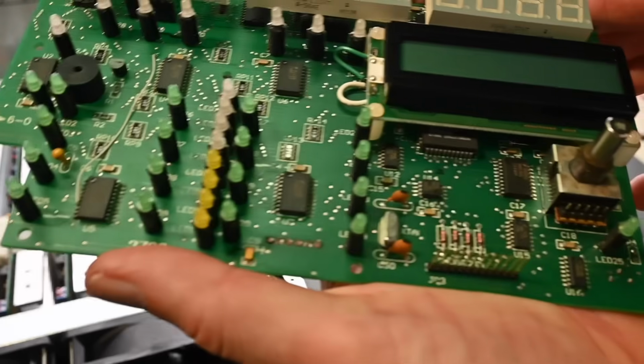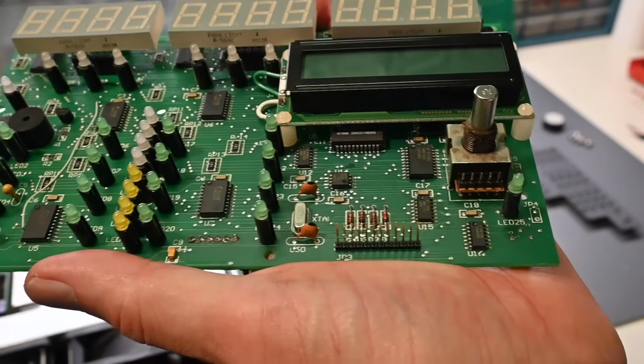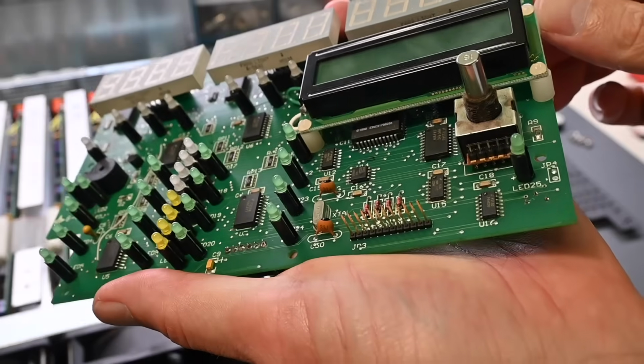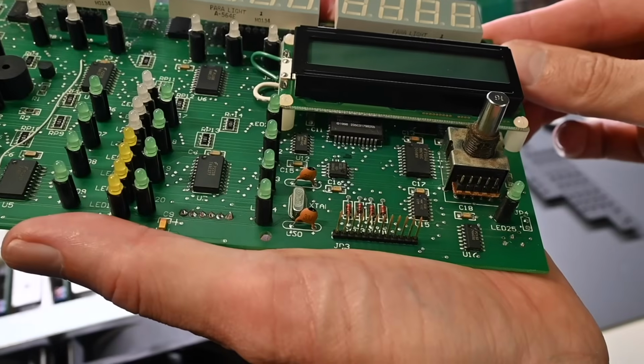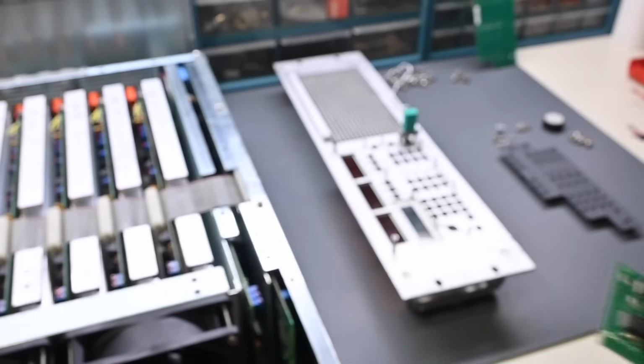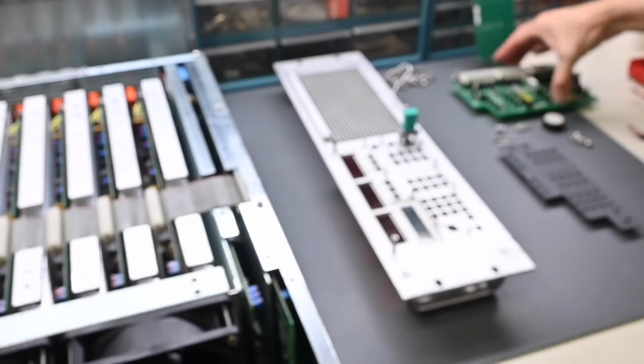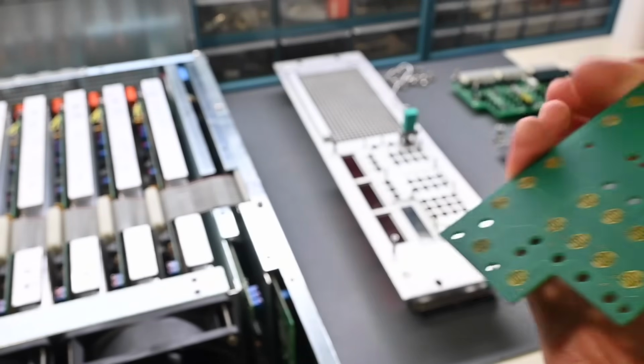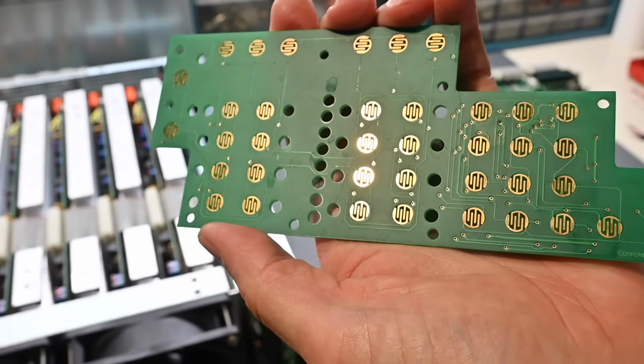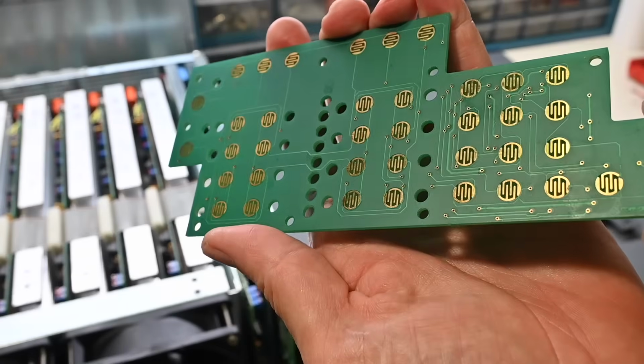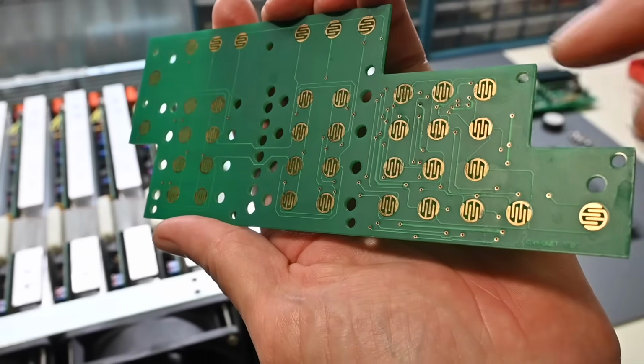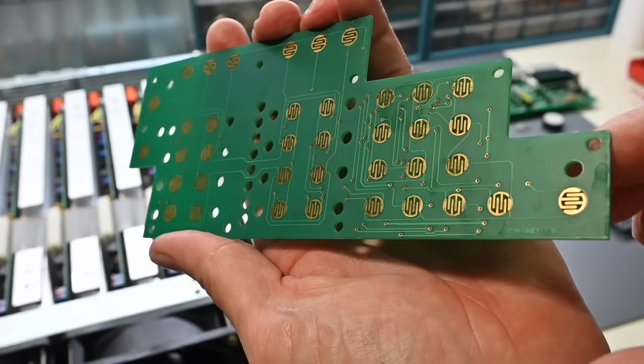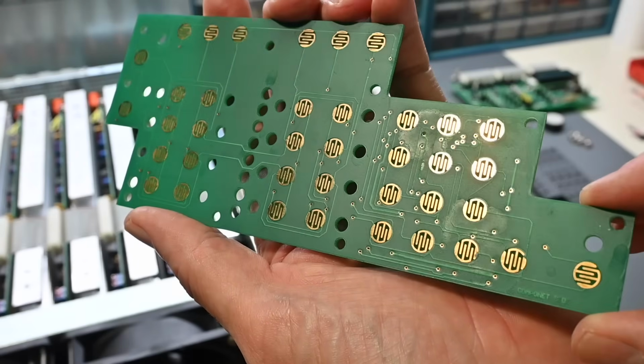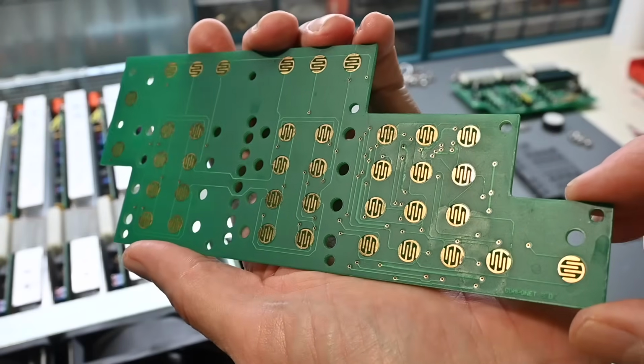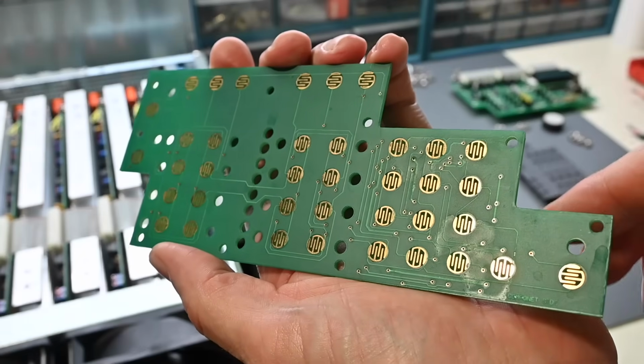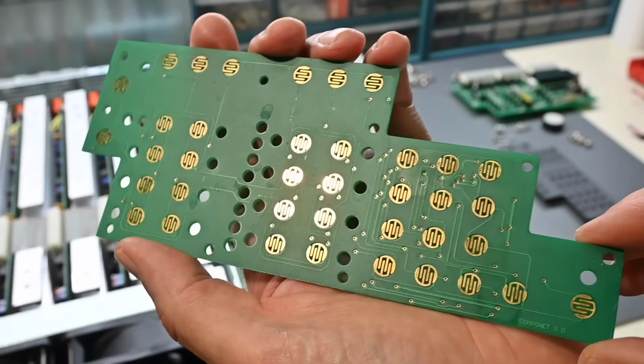And over here you can see the board just needs a little bit of general cleanup. A rotary encoder has kind of a dust and scum built up around it. So I'll get all that taken care of. And if we take a look on this circuit board here, this is for the keypad. And it might not be real obvious on the camera, but those gold-plated traces that make up where the buttons are at for the contacts have kind of a scum and build up on them as well. So I'll clean up all of those. And when those get dirty, you have that issue where you're pushing buttons really hard trying to make a connection. So now's the time to get all that cleaned up.